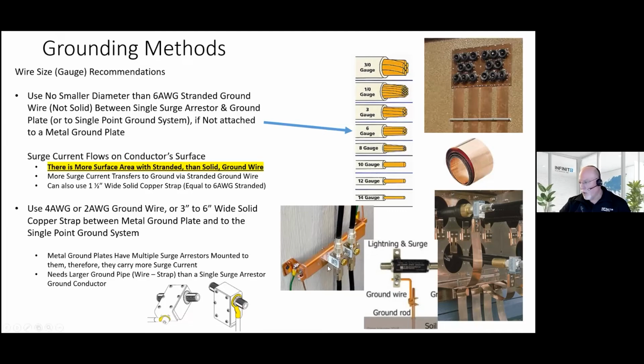If you are attaching it to a ground bar, and you might have multiple surge arrestors like in this image, it doesn't really show it, but the ground path from the ground bar to the ground system needs to be a bigger pipe than 6-gauge, because you're combining surge currents on that bar. So you might want to go with a number 4 or a number 2 gauge from the ground bar. But if you're just going to a single surge arrestor, then the magic number is a 6-gauge stranded. That's an industry standard, but PolyPhaser did their own study many years ago, and their results were that a 1.5 inch wide solid copper strap, which is equivalent to 6-gauge stranded, is as much copper as you need. Anything more than that to a single surge arrestor is overkill.